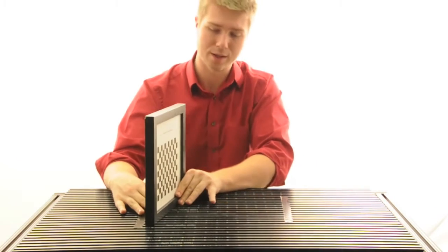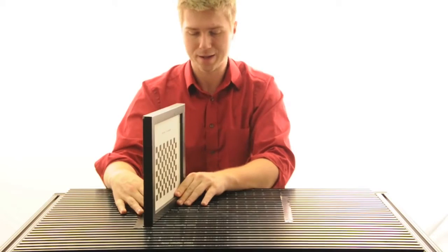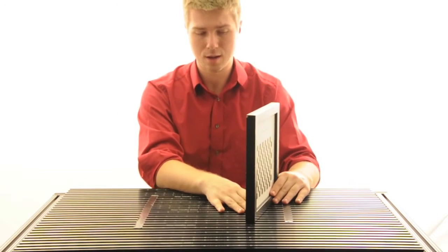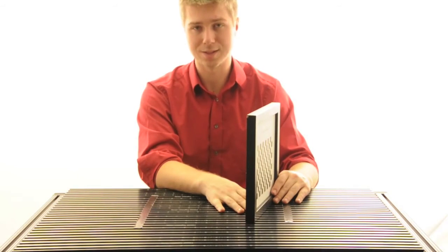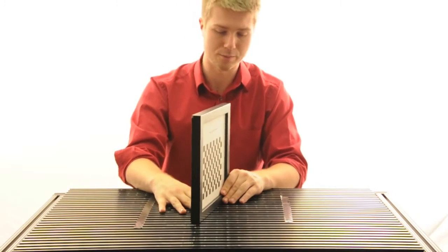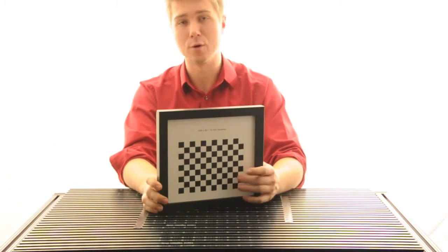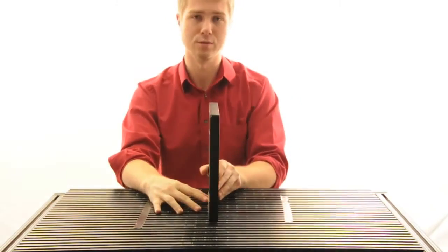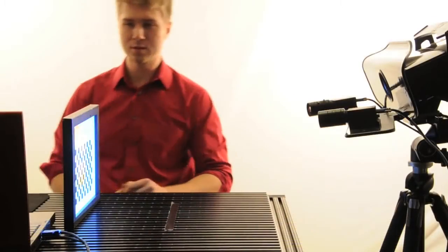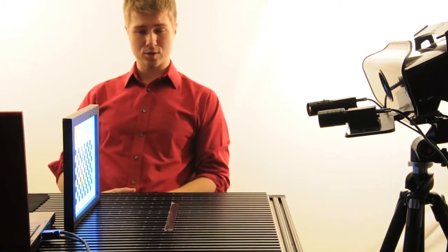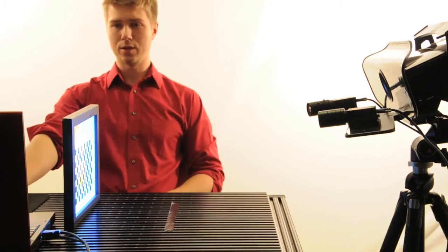The easiest way to know where the back and front of your Z depth or your depth of field should be is by the focus of your focusing pattern on the calibration board. Okay, so let's go ahead and start working on our calibration.